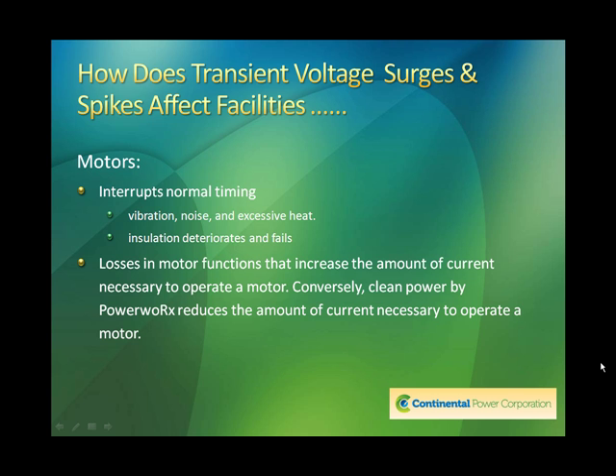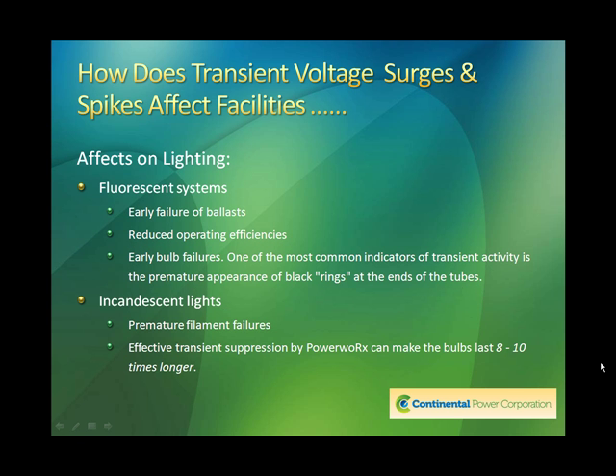Now you take the flip side of that: clean power, like what the PowerWorx is able to provide, reduces the amount of current necessary to operate a motor. And so we see just from this that we do get potentially some savings from ridding the facility of surges and spikes. We see effects on lighting, fluorescent systems, early failure of not only bulbs but ballasts.